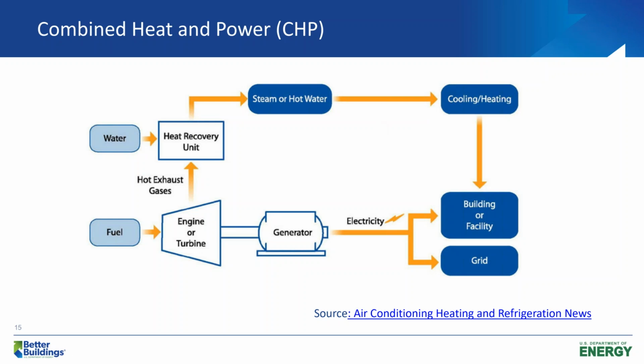CHP is most often used for base load, so it isn't generally used to ramp up and down quickly to meet near-term demand management, but it can be very effective for minimizing costs, especially if you have a campus of buildings that can use that waste heat.